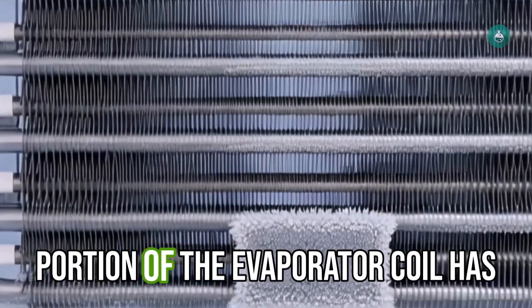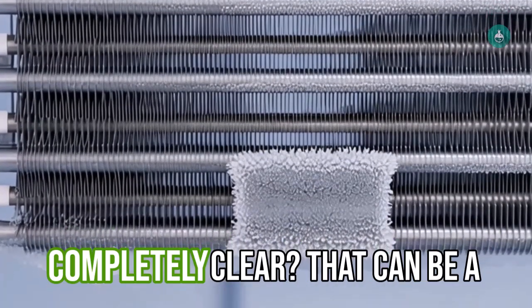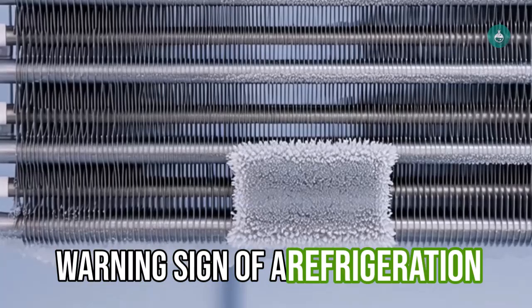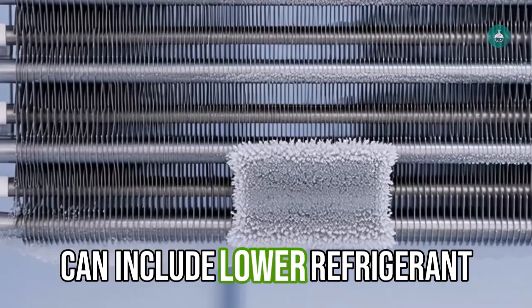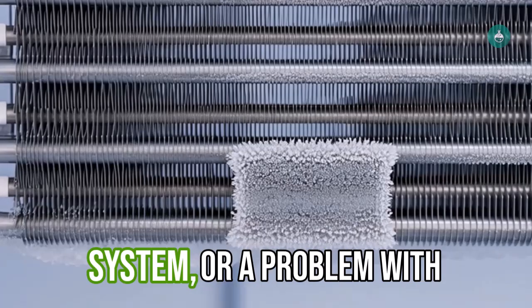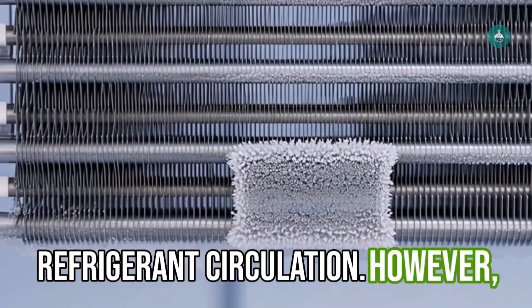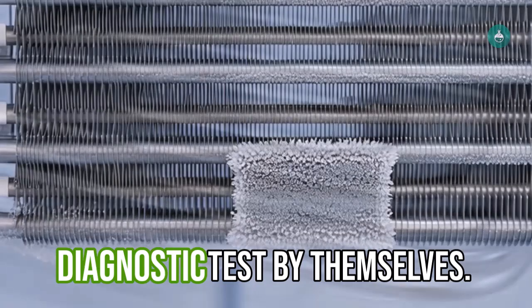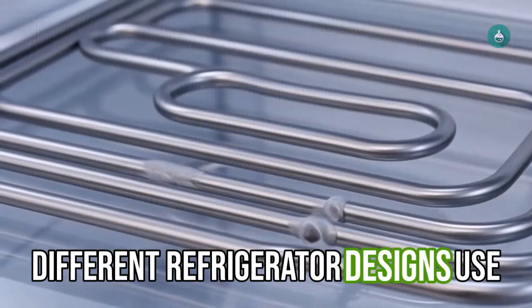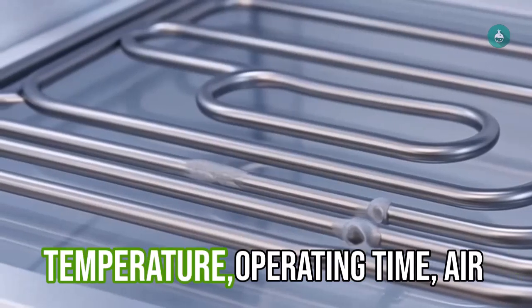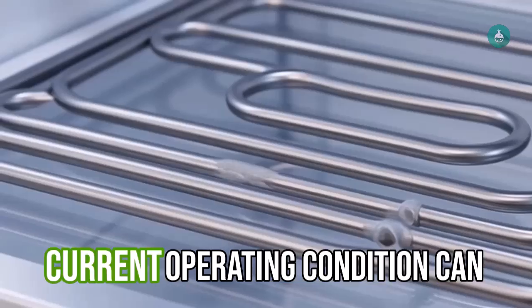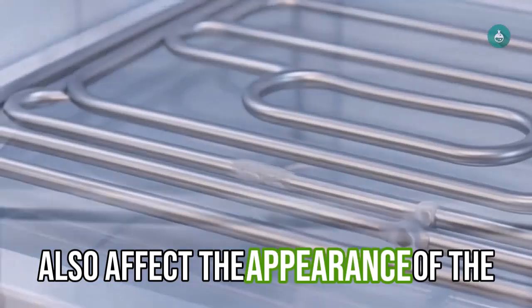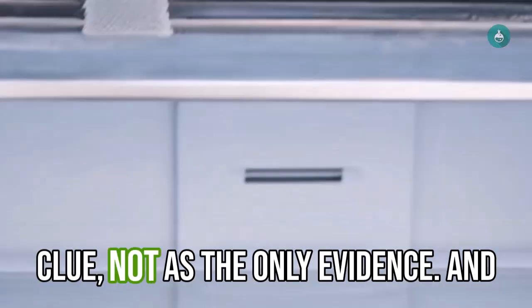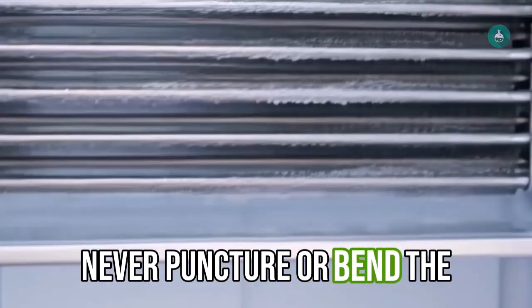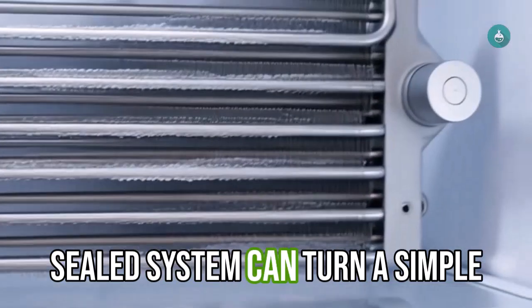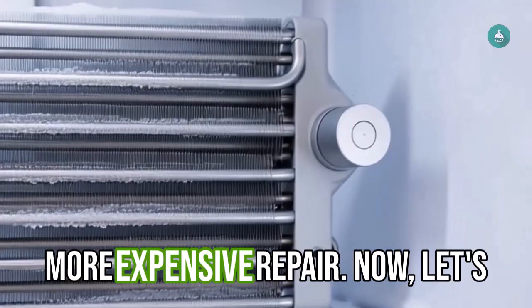But what if only a small portion of the evaporator coil has frost while the rest remains completely clear? That can be a warning sign of a refrigeration system problem. Possible causes can include low refrigerant charge, a restriction in the sealed system, or a problem with refrigerant circulation. However, frost patterns are not an exact diagnostic test by themselves. Different refrigerator designs use different evaporator configurations. Temperature, operating time, airflow, and the refrigerator's current operating condition can also affect the appearance of the frost. So use the frost pattern as a clue, not as the only evidence. And never puncture or bend the evaporator tubing. A damaged sealed system can turn a simple refrigerator problem into a much more expensive repair.